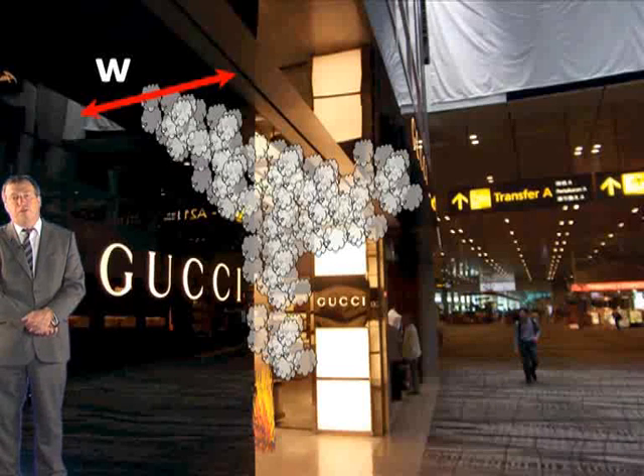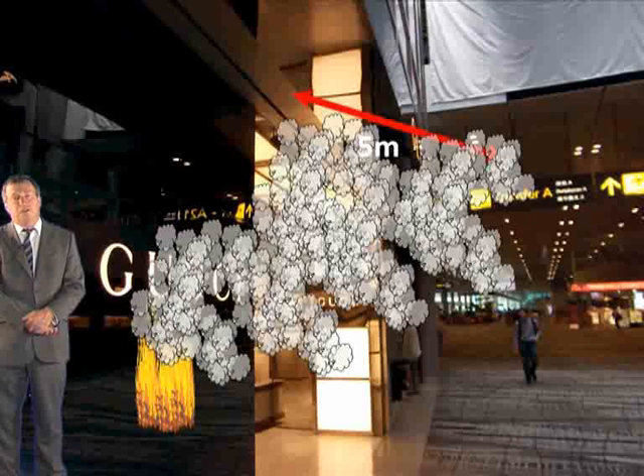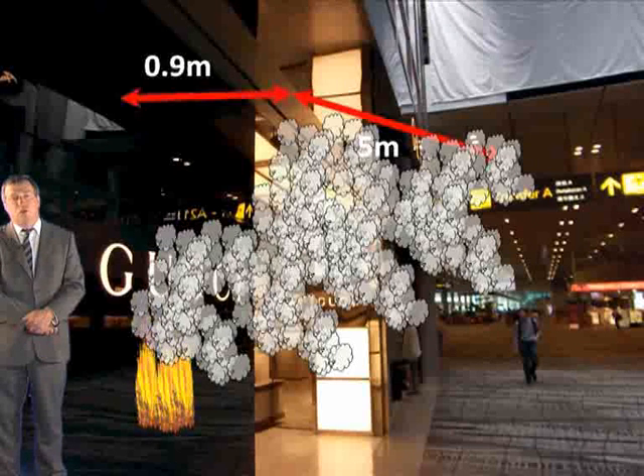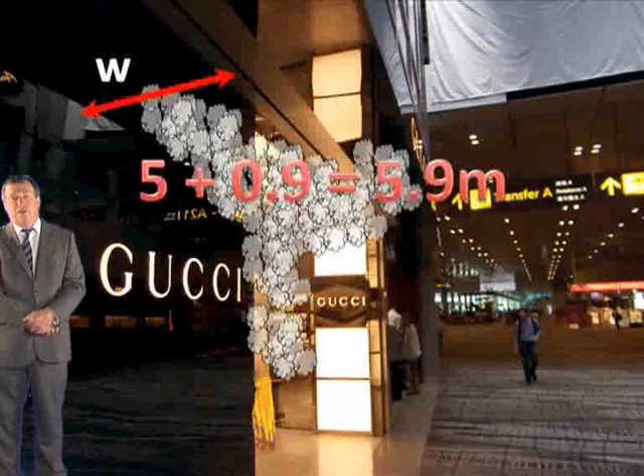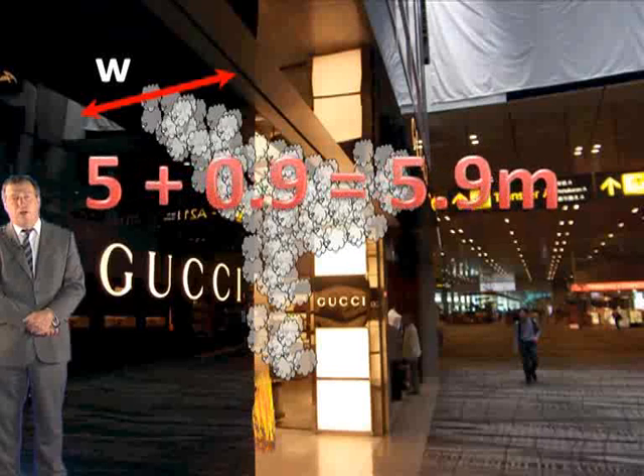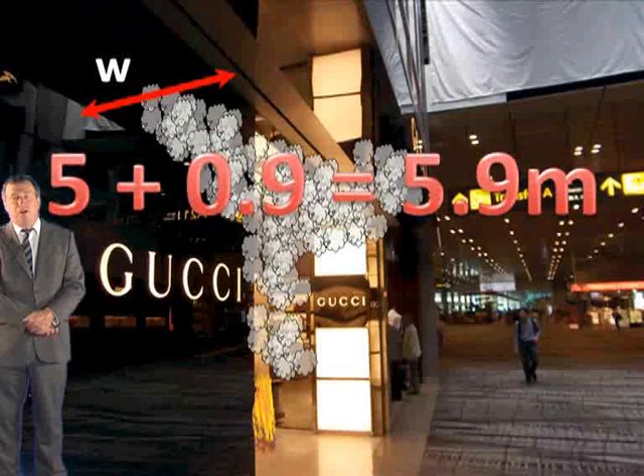So if we have an opening 5 metres wide, and the distance from the opening to the spill edge is 0.9 of a metre, we take the width of the spill plume at the spill edge to be the 5 metres of the opening width plus the 0.9 of a metre of the distance from the opening to the spill edge. So that's 5 plus 0.9, which equals 5.9 metres. The depth is, of course, of little importance in this case, as we're not providing channeling screens.